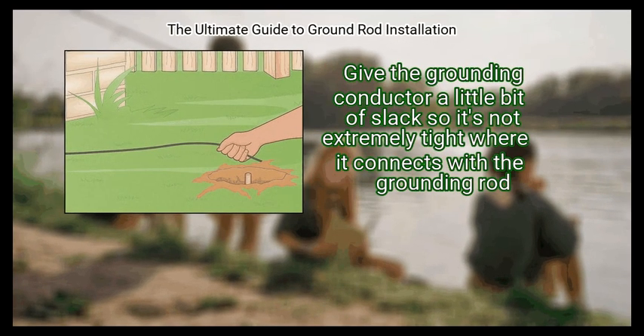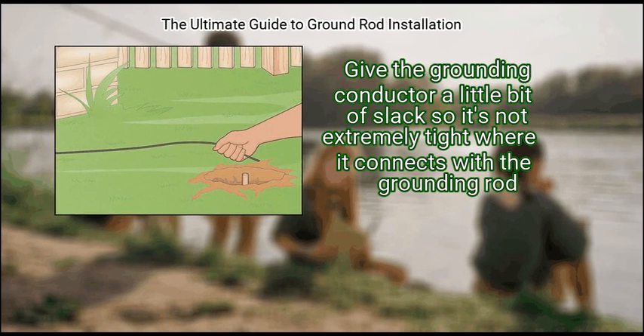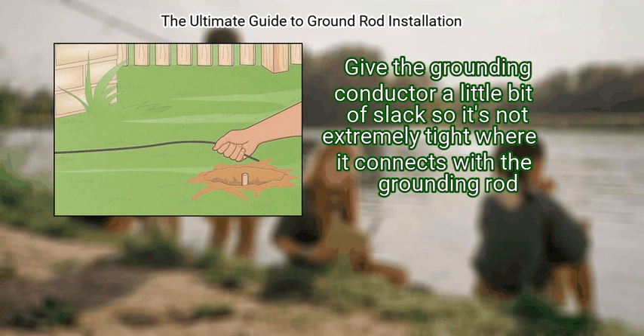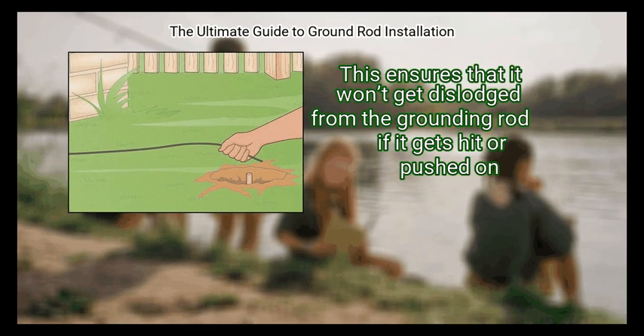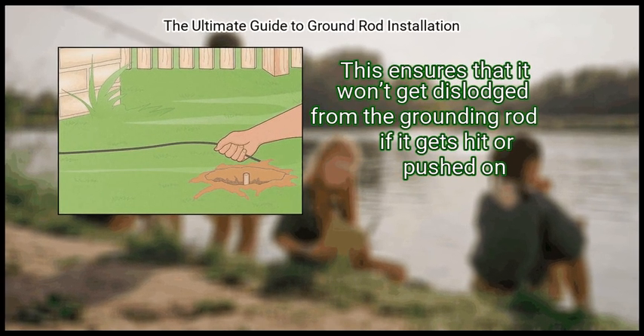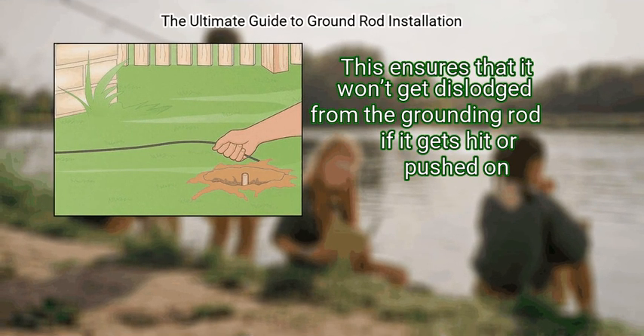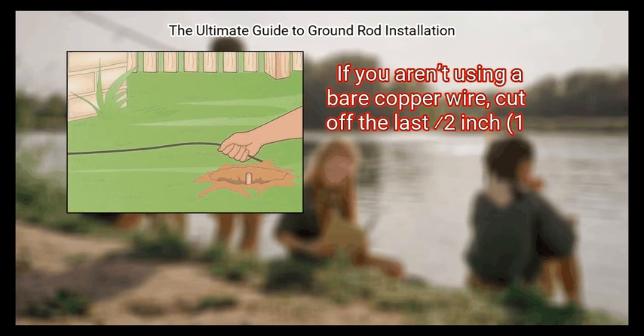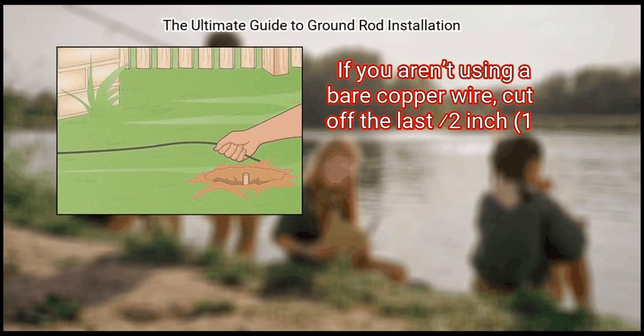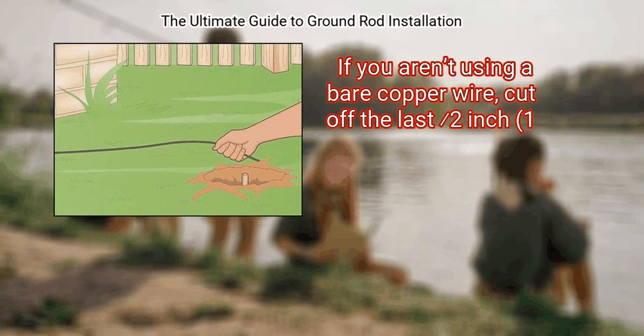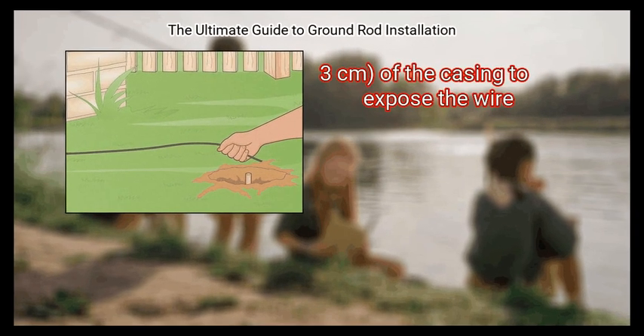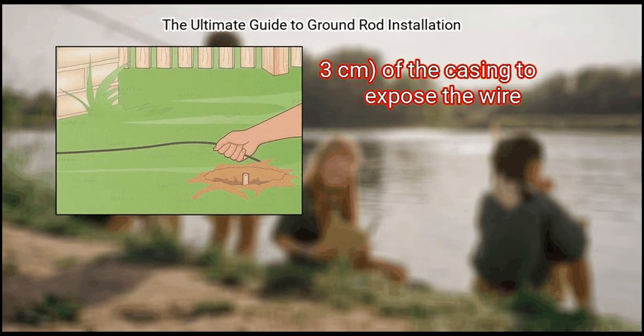Give the grounding conductor a little bit of slack so it's not extremely tight where it connects with the grounding rod. This ensures that it won't get dislodged from the grounding rod if it gets hit or pushed on. If you aren't using a bare copper wire, cut off the last 1/2 inch (1.3 cm) of the casing to expose the wire.